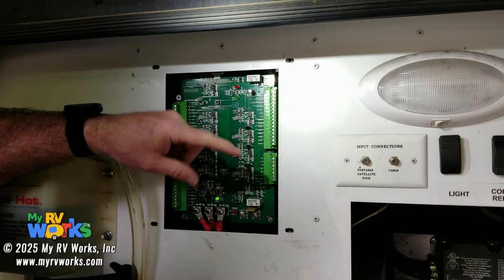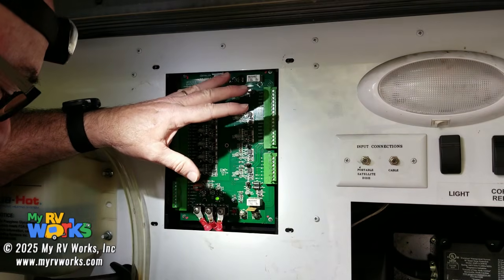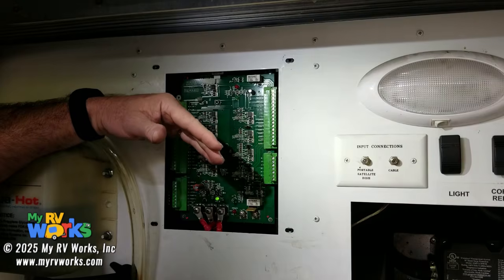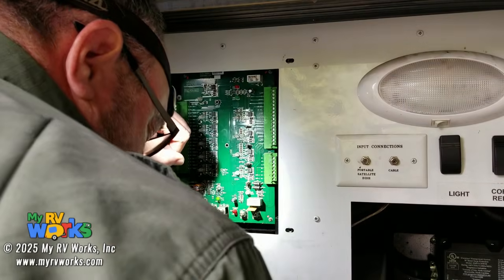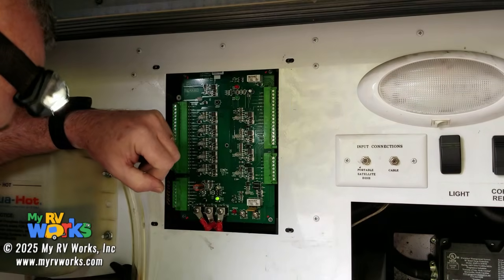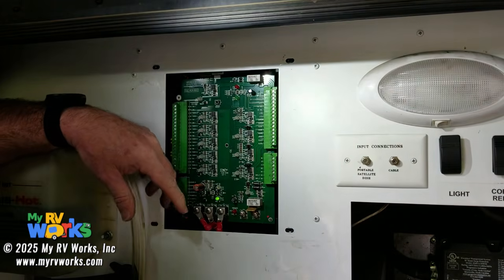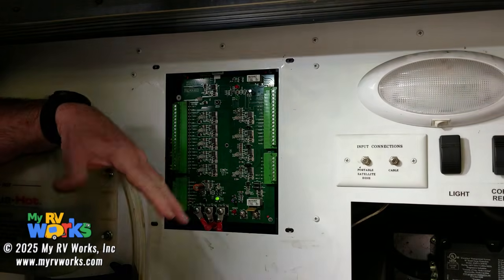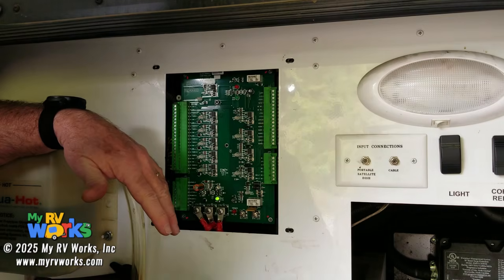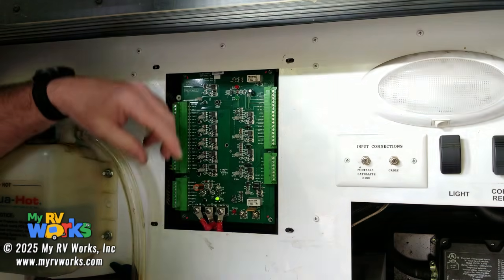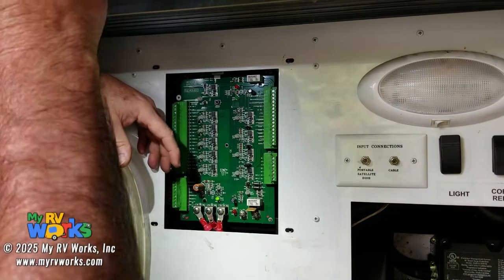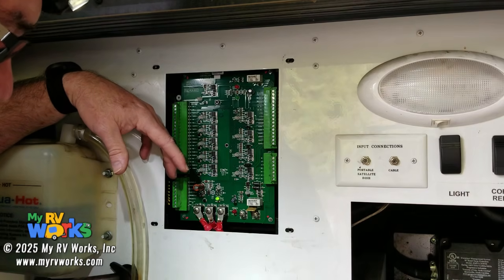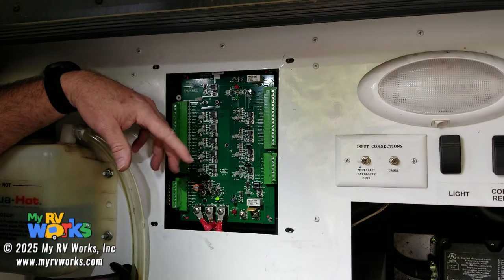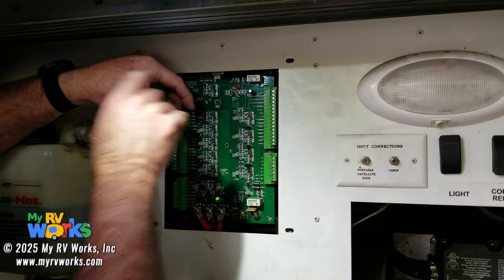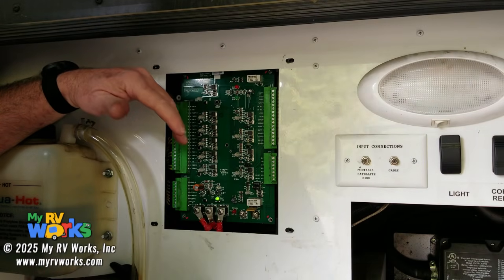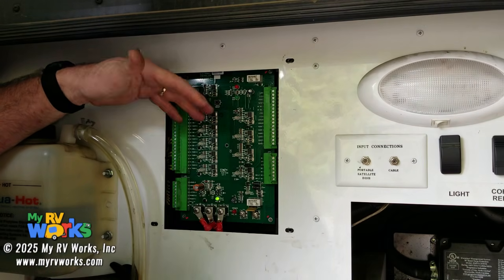So if your AquaHot is at temperature and everybody's happy, the AquaHot takes about 15 minutes plus or minus, depending on ambient temperature and all these other variables. The AquaHot takes about 15 minutes to go from ambient temperature, right now about 65 or so, up to 180 degrees. When it gets to 180 degrees, the AquaHot will turn off, but your status light will stay on, meaning I am satisfied, but I will start back up again if I need to.